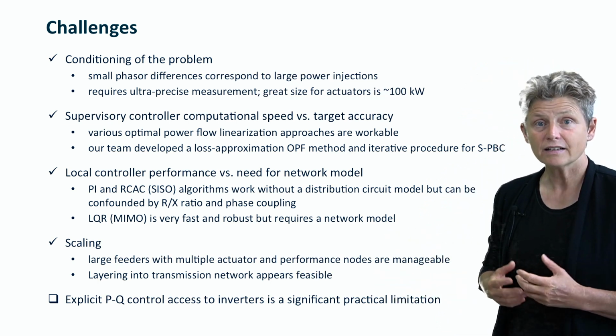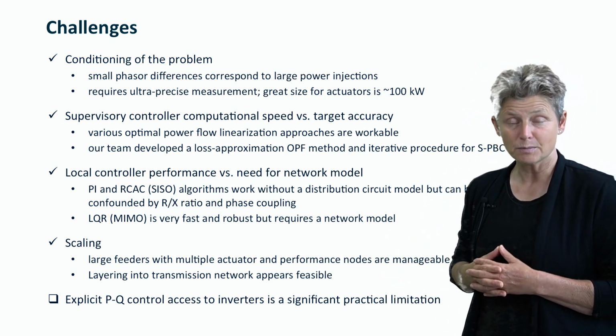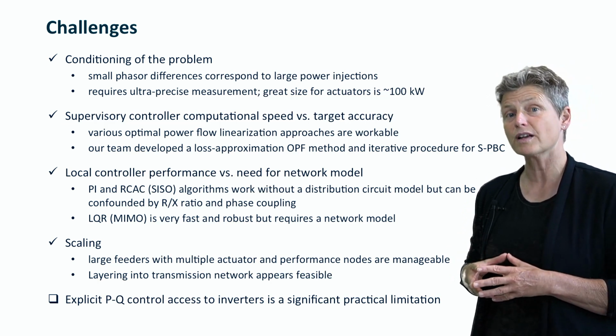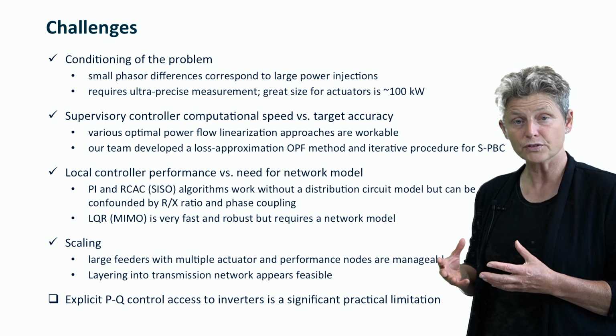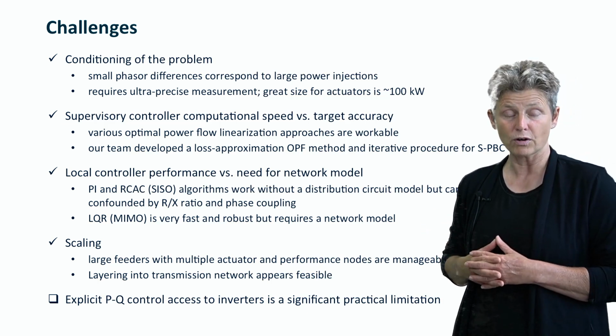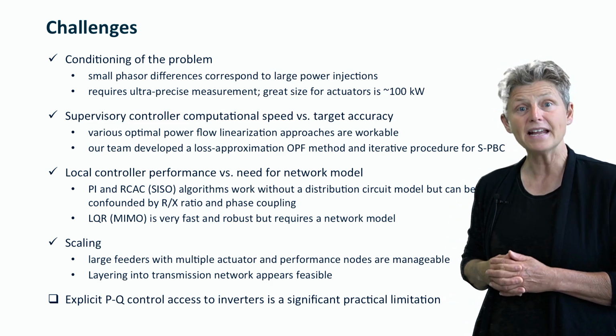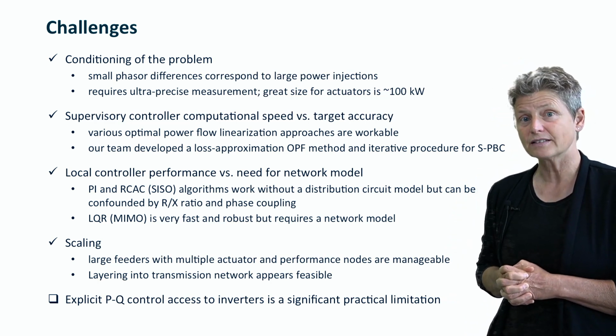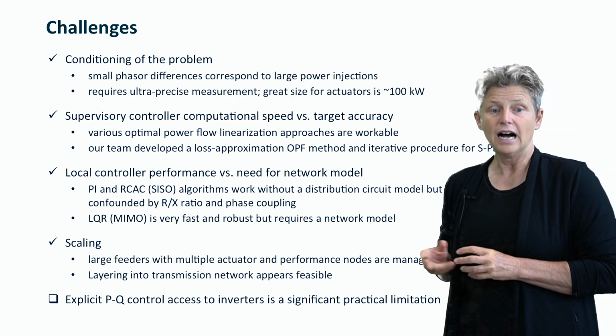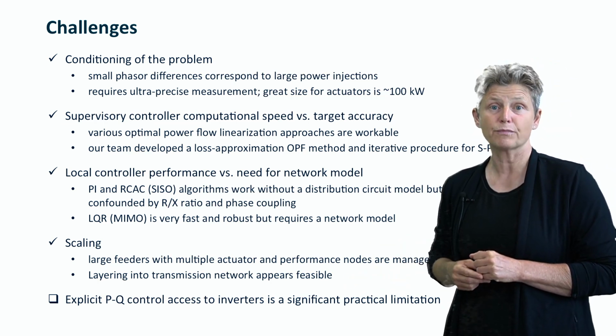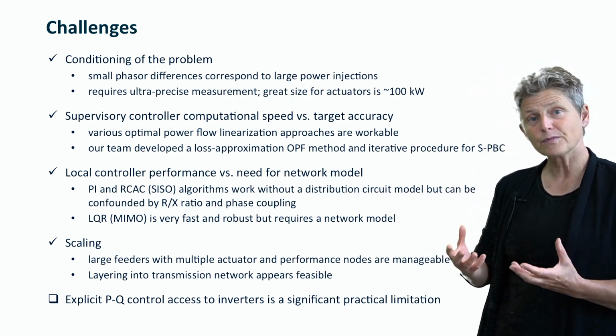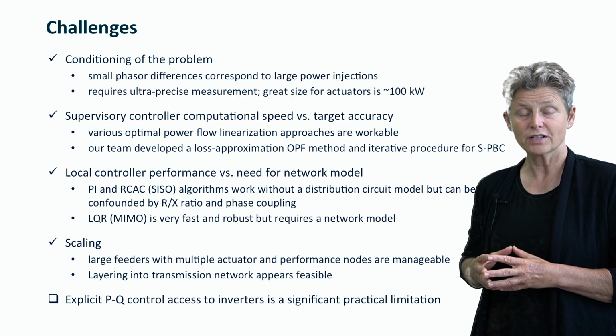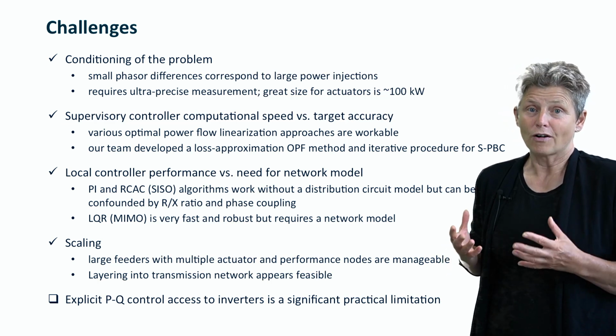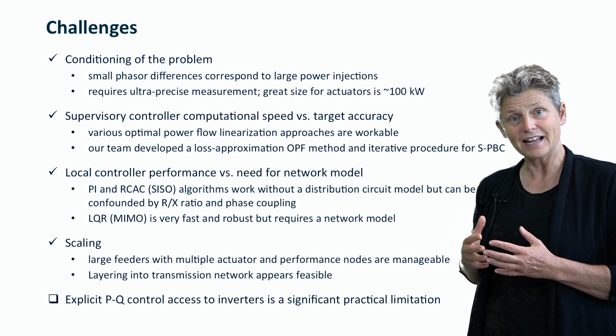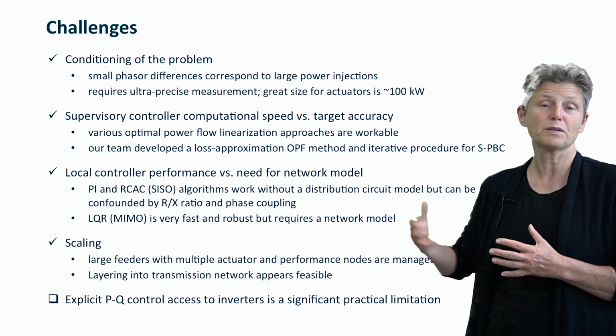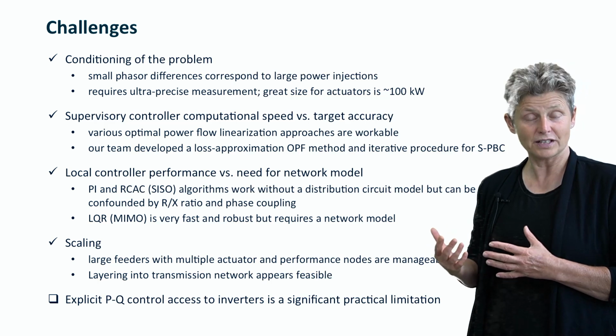Finally, scaling should work. In simulation, there's no reason to think that we would run into any showstoppers if we work with bigger circuits, bigger networks. Really the main issue, the main challenge that we haven't addressed is having explicit real and reactive power control when talking to inverters, because inverter manufacturers are a little protective of what's under the hood there and don't necessarily want their devices to be responding to all kinds of different inputs externally.